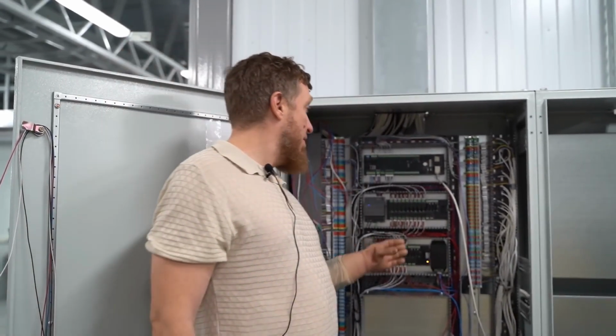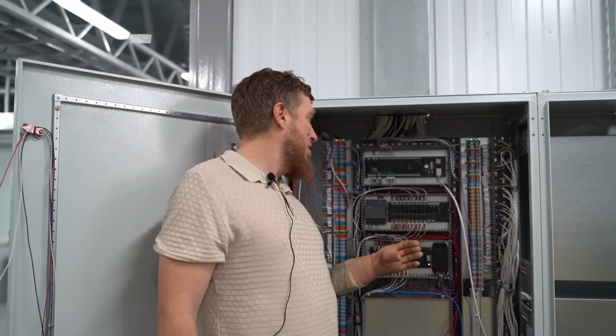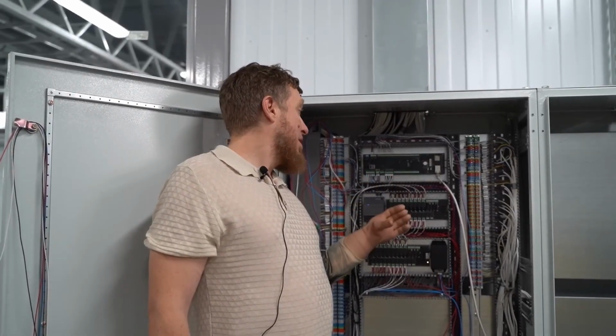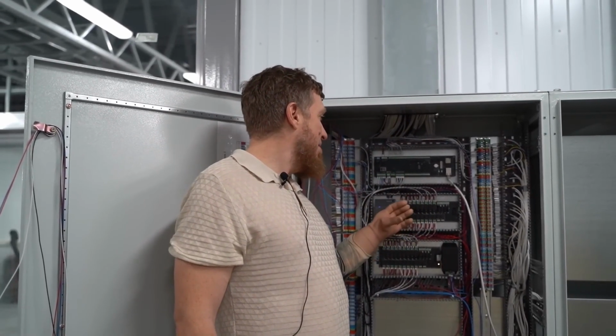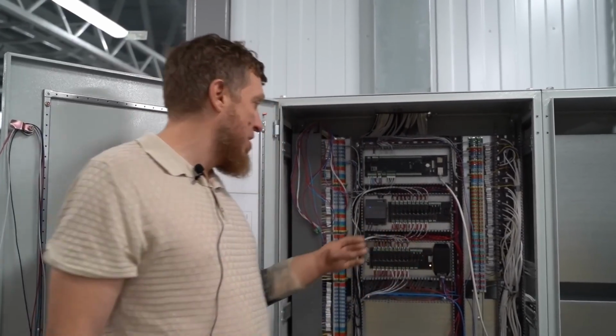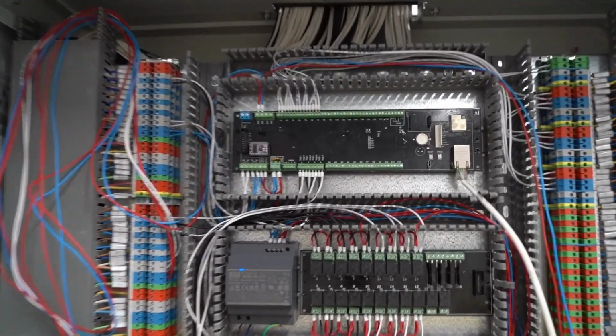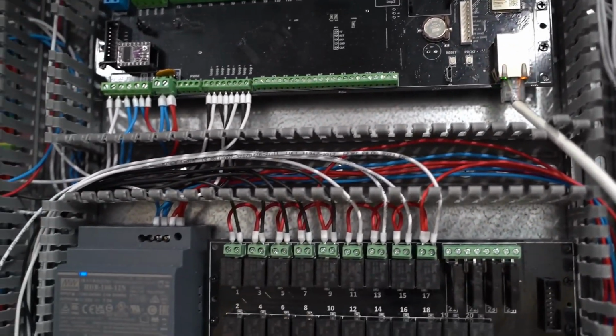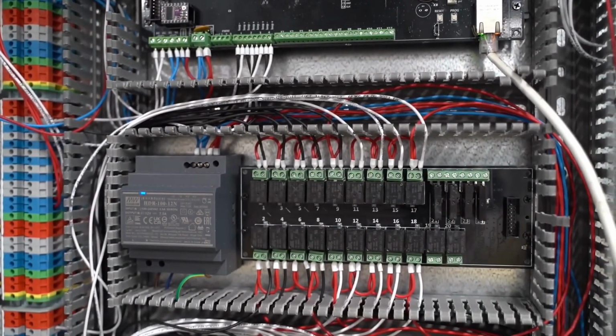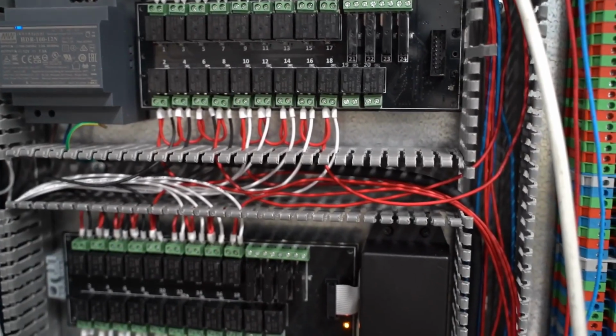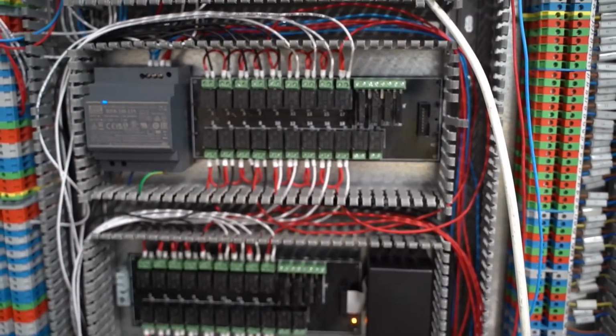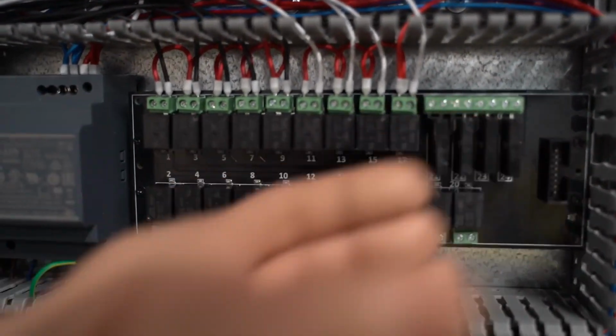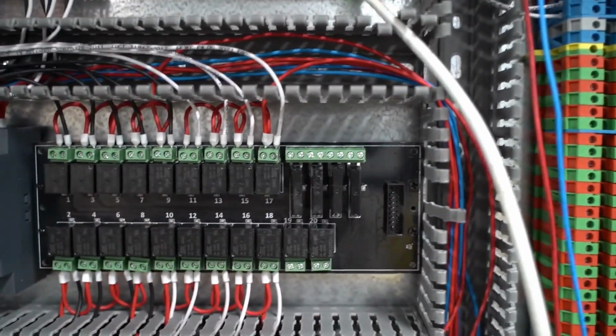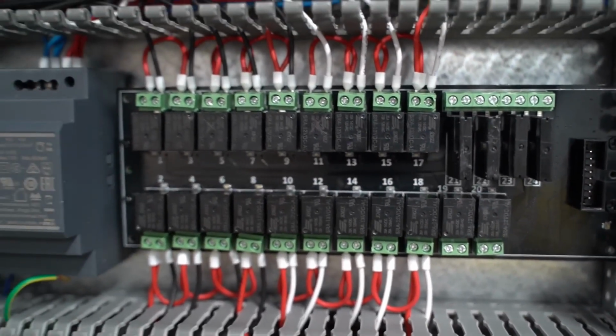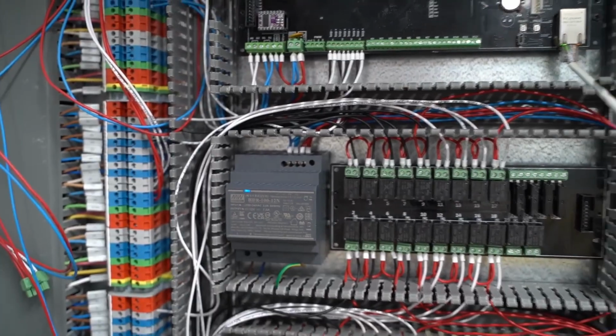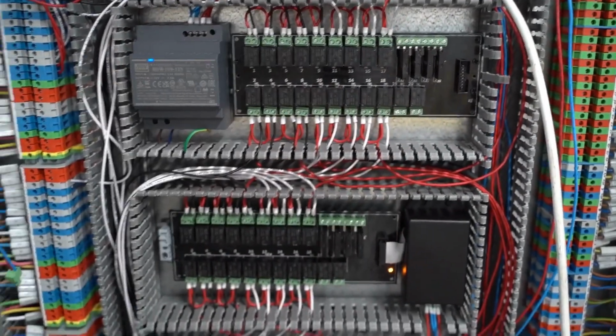The controller itself features digital inputs, 4 to 20 milliampere current inputs, and 0 to 10 volt analog inputs. Then there's a PWM output, and there's also a dedicated output for heat meters that operates using PWM pulse signals. For heat meters, that's typically achieved with a Hall sensor, or for other types of devices as well, it can detect pulses. Basically, these relay boards here are equipped with solid-state relays for 3-way valve actuators and standard 10 amp relays. They're all connected through our interface box, which is capable of handling up to 4 such relays at the same time, and it also features a Modbus output for communication.